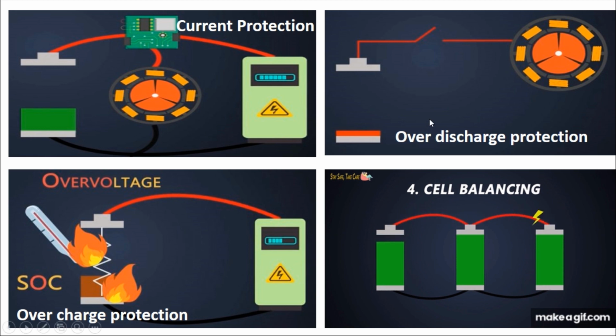Lithium ion batteries have around 70% to 80% depth of discharge. Let's consider 60% - around 60% of charge you can take from your battery, and 40% needs to remain in the cells. That's the reason BMS is used, to protect the battery from undercharge, and because of this protection, you protect the battery from getting damaged in terms of life cycles. So we have overcharge protection and over-discharge protection.